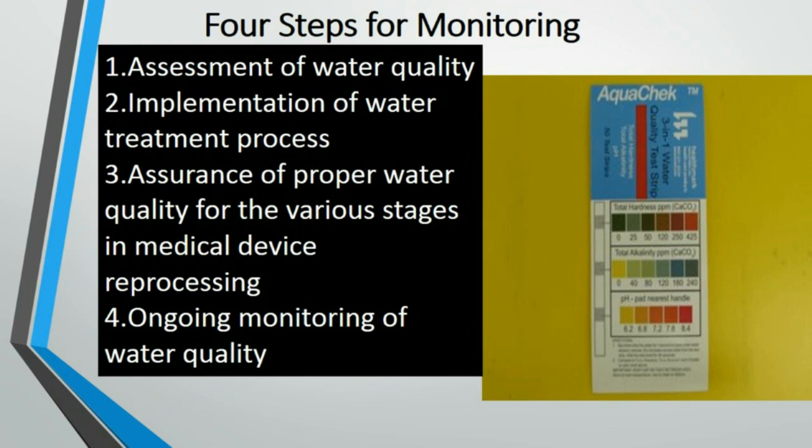Four steps for monitoring. You want to assess your water quality. You want implementation of a water treatment process, assurance of proper water quality for various stages in your device reprocessing, and then ongoing water quality monitoring. And you can sort of think about that: there's a way to start, here's how I'm going to do it, and here's how I'm going to continue to make sure that it is working properly as I move on.